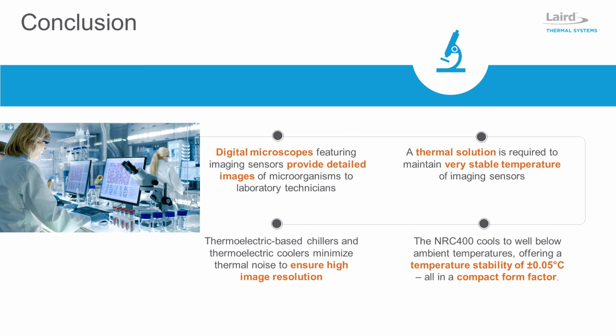Digital microscopes utilize CCD or CMOS sensor-based cameras to capture high-resolution images of microstructures. A thermal solution is required to remove waste heat and maintain very precise temperature control of imaging sensors. Thermoelectric chillers, in combination with thermoelectric coolers, minimize thermal noise in imaging sensors to achieve maximum image resolution. Utilizing next-generation thermoelectric coolers, the NRC400 Performance Chiller delivers 400 watts of cooling power and a temperature stability of plus or minus 0.05 degrees C, which exceeds requirements for microscopy imaging applications.